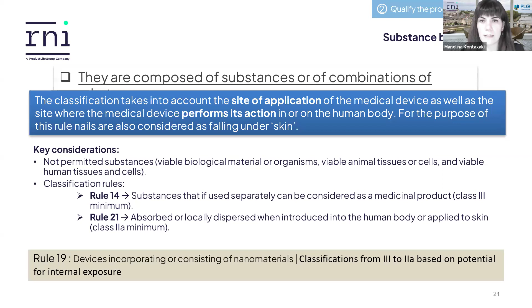Let's see here some examples of Rule 21 and which class applies depending on the intended purpose and the application site. If we are going to apply the medical device into the human body or via a body orifice, and we know that the combination of substances or the substance is going to be systemically absorbed, then the product is directly Class 3. If we also have a medical device whose intended purpose is in the stomach or in the lower gastrointestinal tract, and maybe the substances or their metabolic products are going to be systemically absorbed, then the product will also be classified as Class 3.